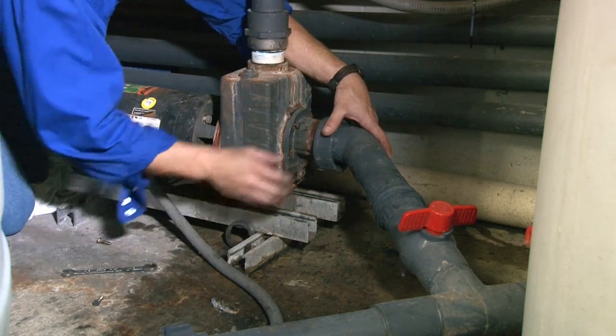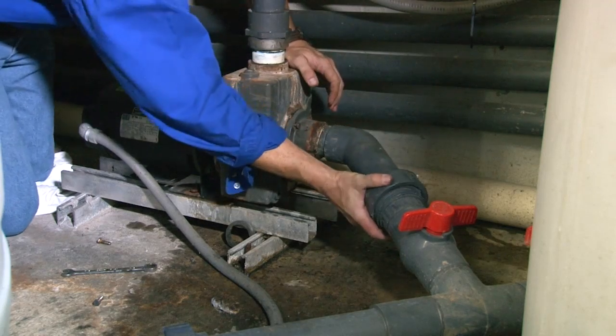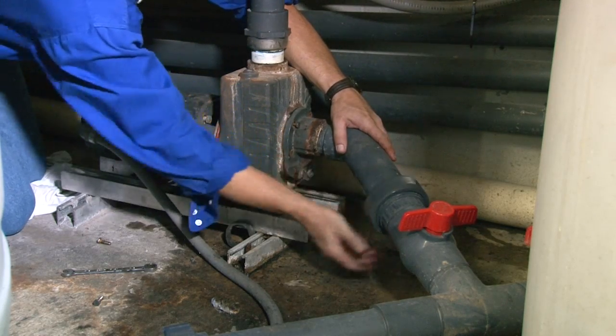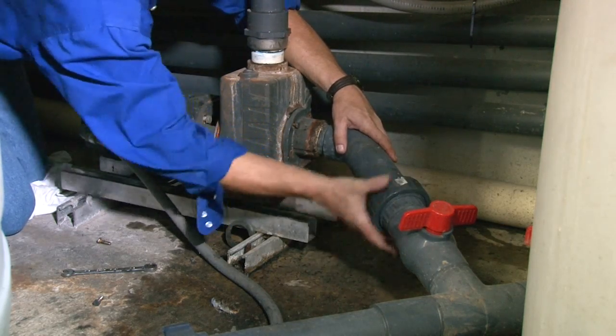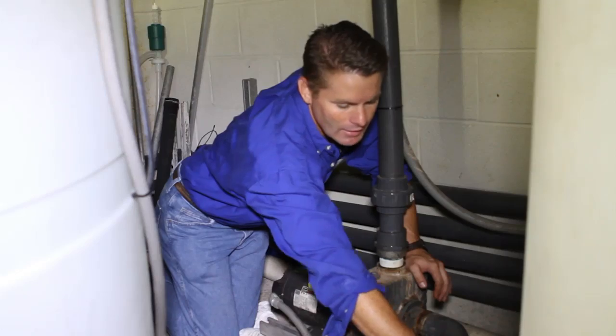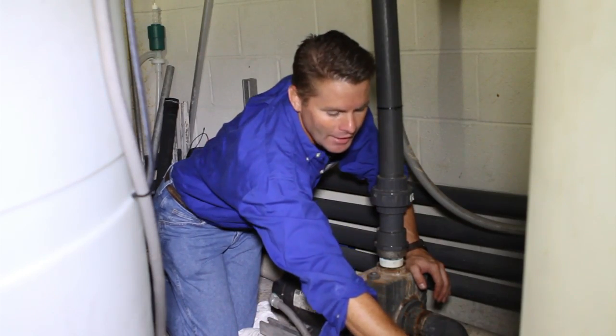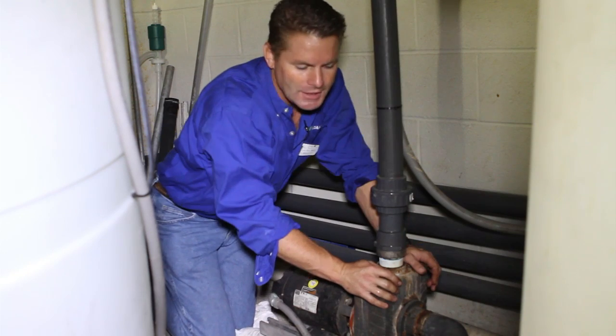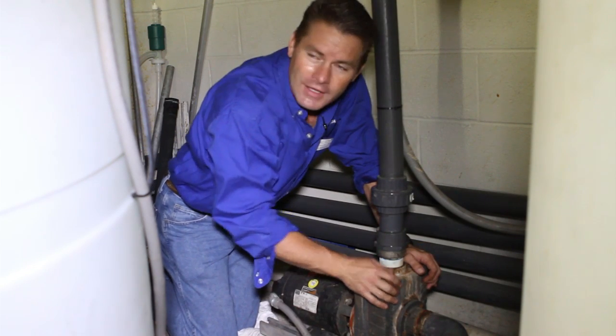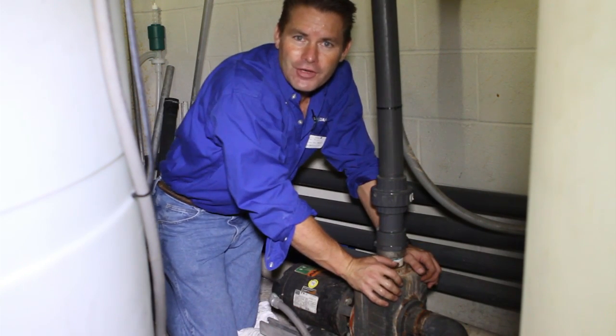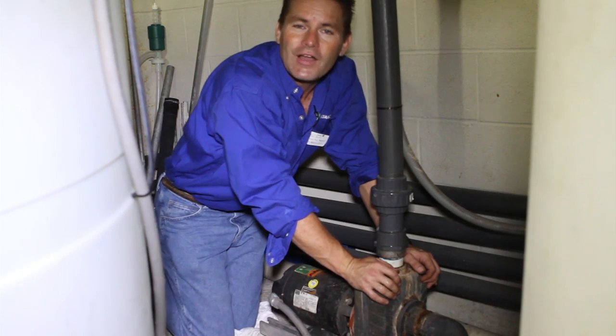So I'll put the rest of the bolts in, reconnect my union nice and tight. I can turn my water valve back on and make sure I don't have any leaks in my pump heads. If everything's not leaking, you can go ahead and turn the breaker back on, and your pump should start pumping back to normal. And that completes this video.